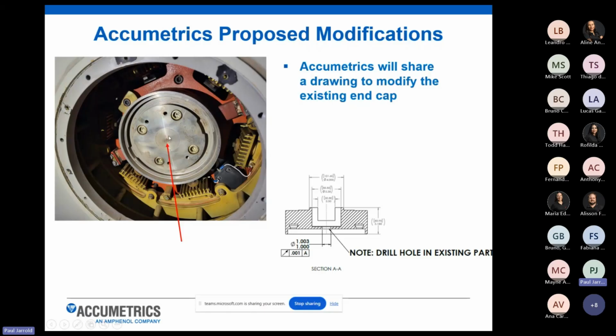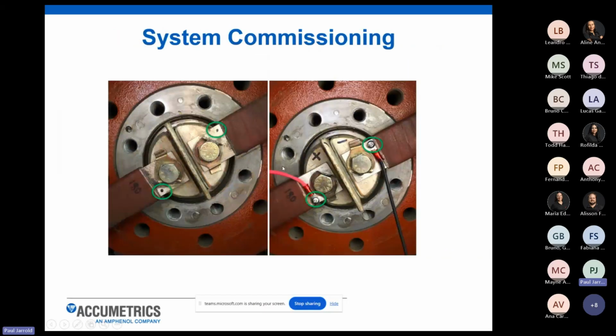We basically need to have a hole drilled in the center of this rotor end cap so we can route the electrical connection to the field bus bars through the center of that. And you can see the bus bars kind of in the background here. So there would be a plus and minus connection to the field windings directly underneath this rotor end cap. So that's what that looks like.